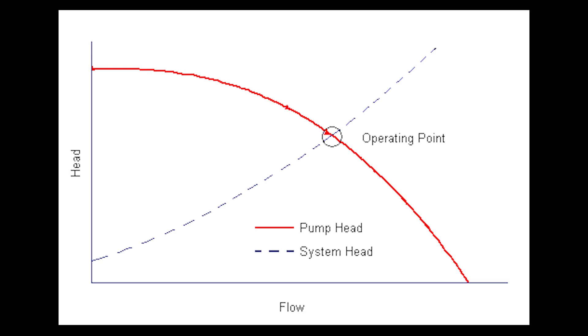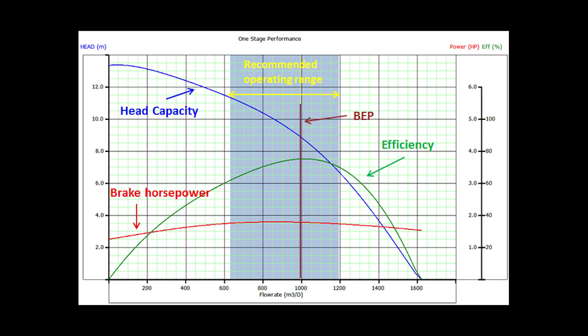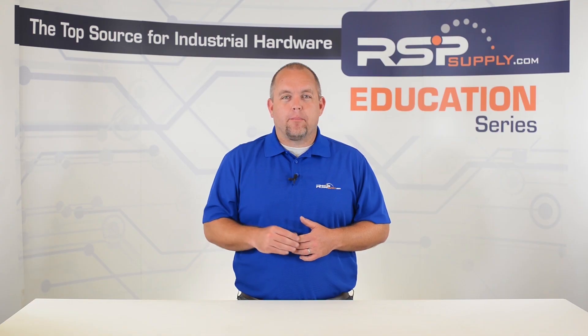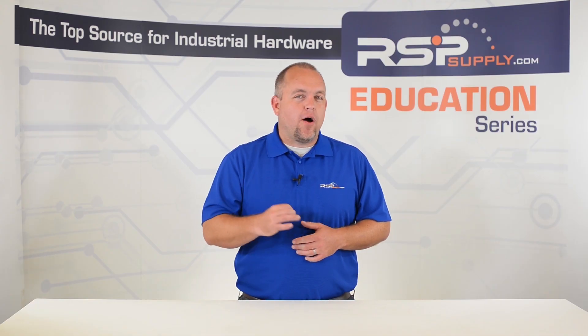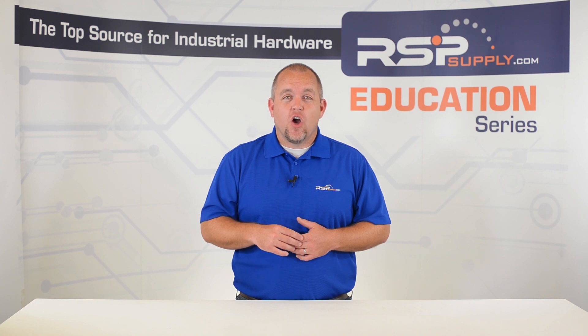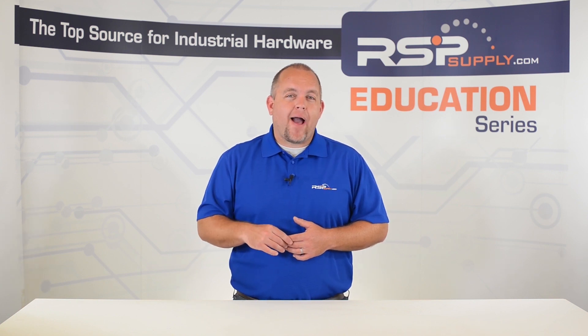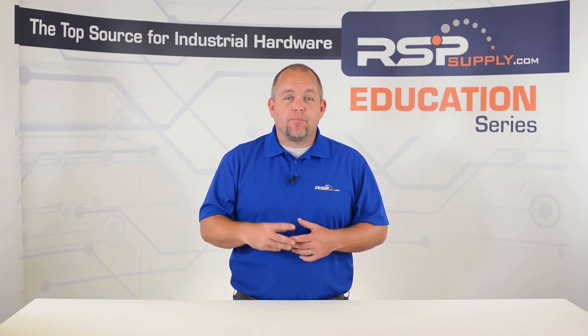With this information, the pump curve will typically offer the most efficient way in which to use the pump. The efficiency of a pump is the relationship between the input horsepower required to drive the pump at a given operating condition and the water horsepower being created by the pump. No pump is 100% efficient, always requiring more power than can be released.